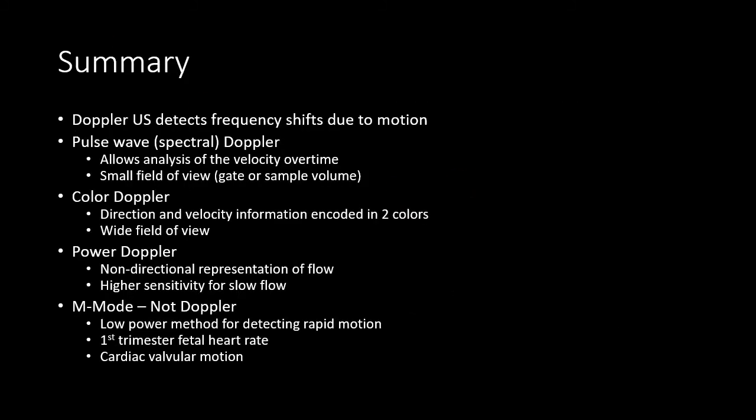In summary, Doppler ultrasound detects frequency shifts due to motion. Pulse wave or spectral wave Doppler ultrasound is a quantitative form that allows for the measurement of velocity over time, but is limited by a small gate or sample volume and has a relatively high thermal and mechanical index. Color Doppler ultrasound is a more qualitative form where direction and velocity are encoded in typically two colors with variable brightness, with a wider field of view than pulse wave Doppler. Power Doppler is a non-directional representation of flow whose main advantage over color Doppler is higher sensitivity for slow flow. M-Mode is not truly Doppler, but is a good low power imaging modality for detecting rapid motion, used predominantly for determining first trimester fetal heart rate and evaluating cardiac valvular motion.